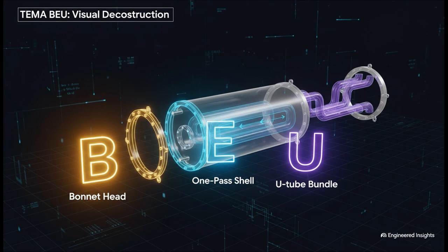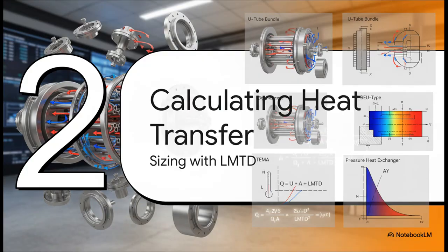So let's break that code down with a super common example, the BEU type. The B tells us about the front head, in this case, a bonnet head. The E is the shell type, just a simple single-pass shell. And the U is the rear head, which tells us we've got a U-tube bundle. Now this U-tube design is really clever, especially for maintenance. Since the tubes are bent in a U and only attached at one end, you can pull the entire bundle right out of the shell. This makes cleaning or repairs so much easier, a huge win in services where you know you're going to get a lot of gunk building up. So, we've picked our BEU configuration.